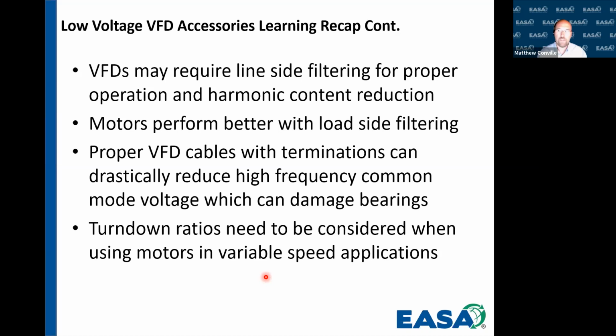And lastly, if we're going to reduce the speed of the machine, again, we're already in violation of what we would consider for a service factor. We really need to take a look at, should we be using a turn down ratio since we're going to be operating in variable speed, so that even though we may not have a winding failure, maybe we're not going to be able to provide enough cooling air to actually cool the bearings appropriately.